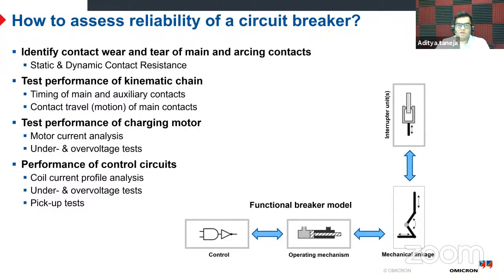Again, these coils are small copper wire coils which have a moving part inside, and they are very sensitive because they are not high rated, they are very short time rated, they have to be very quick, so they are very delicate. So the force which is needed is proportional to the current, and we try to check that with minimum pickup tests. So this is a kind of framework where you can see what you should consider while preparing for maintenance of breakers.